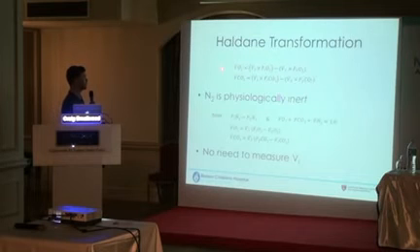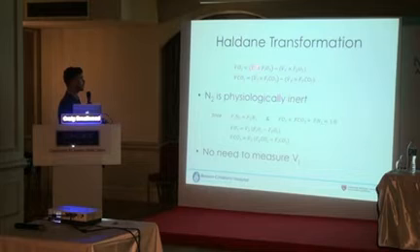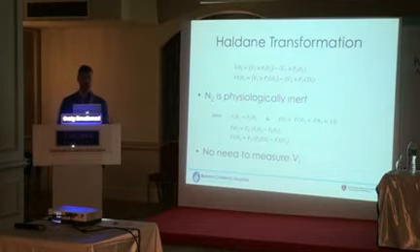But for VO2 and VCO2, this would have been the equations to put all those things together that we just talked about. So to step through this, for oxygen consumption, we have inspired gas volume or flow, inspired concentration, minus expired volume, expired flow, and then you can get the volume of oxygen that's consumed. And similarly for carbon dioxide elimination. So what the Haldane Transformation tells us is we don't want to measure all this stuff. And I think this is of interest to people who build devices because they want to spend less money and they want to make the device as simple as possible, which also has clinical benefits because they'll be more reliable and less likely to break. So the more simple, the better.